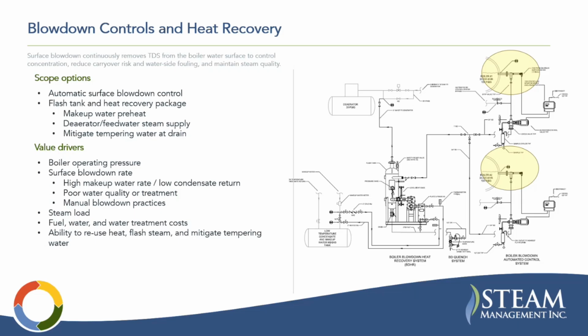So you can capture that in a blowdown heat recovery system, which is basically like a flash tank and heat recovery package where you preheat makeup water. That's probably the most common application for the heating. You're going to capture some flash steam and use that in your deaerator, and then you're going to mitigate tempering water requirements at drain, which we'll talk about in a minute.